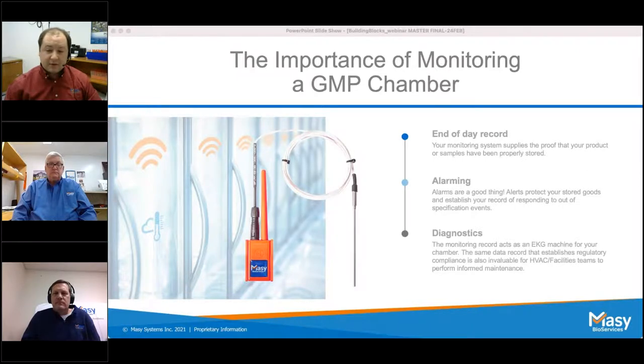With features like these, you can get alarms swiftly sent to the right people and avoid alarm fatigue by having alarms trip only when there's a situation that truly needs attention. Monitoring data also acts as an EKG for your chamber — if put in place early in a chamber's life, it's easy to determine what your healthy chamber looks like. HVAC and facilities teams can utilize this data for well-informed maintenance decisions. Some companies add sensors to compressor or steam systems at strategic locations that can predict failures days, weeks, or even months before they occur.